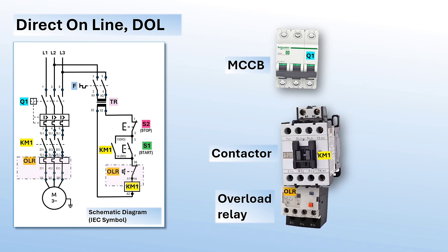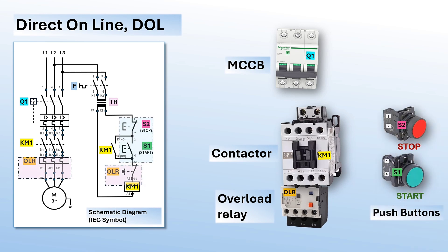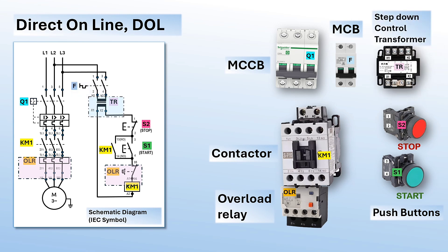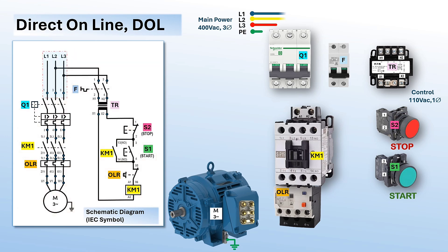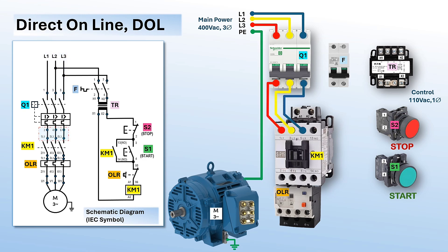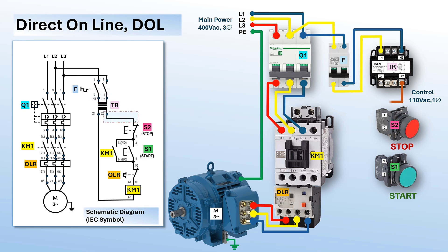The secondary components are control devices. Their requirements vary depending on the application of the motors driving the equipment. For this lecture, we use start and stop push buttons with momentary held contacts, a miniature circuit breaker or MCB, and a step-down transformer for the control circuits. This is a sample schematic diagram of a DOL starter. The diagram has two sections: the power and the control diagram. Please note that in some DOL starter setups, a control transformer is not required if the contactor coil and other control devices have the same voltage rating as the main power supply.